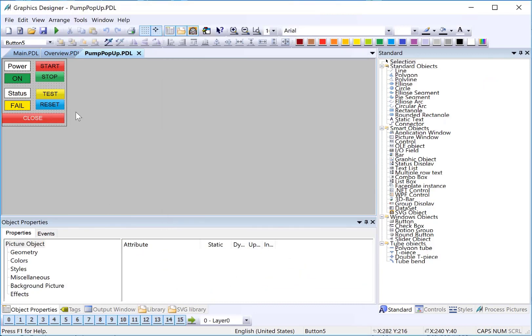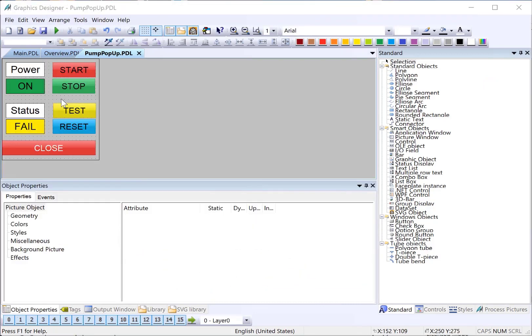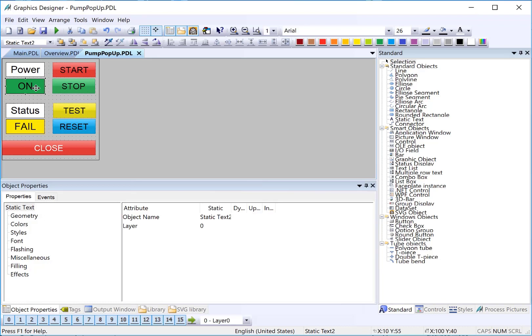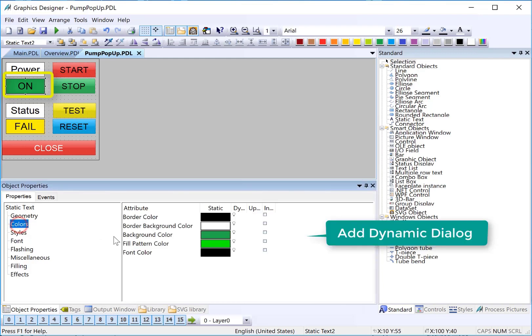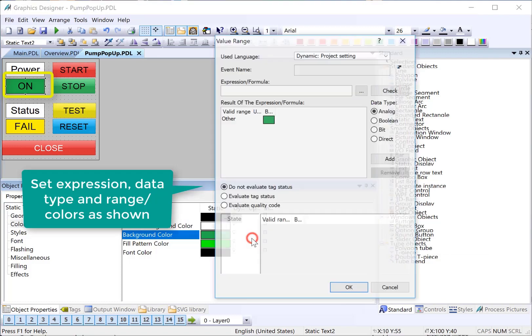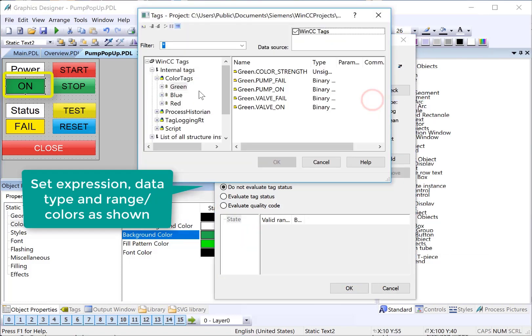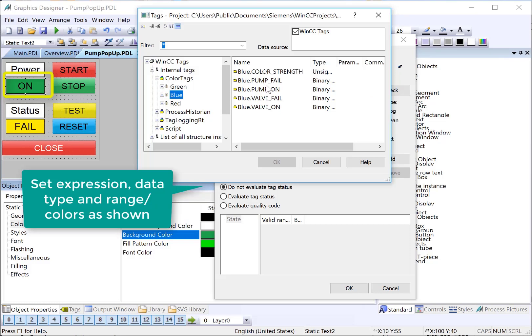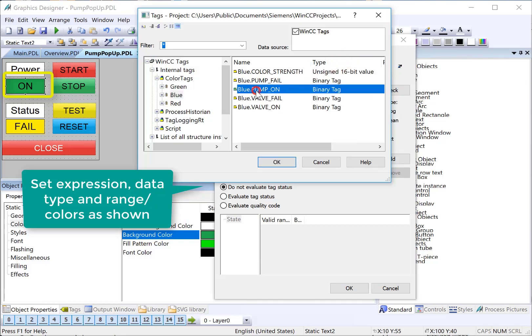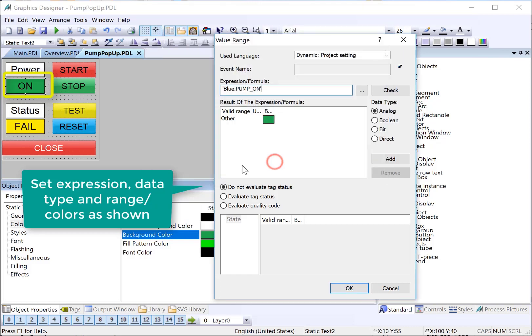And there's our pop-up screen. This pop-up screen is going to map to our color structure, so we need to add dynamics. We'll start with our on-off indicator. We're going to change both the text and color like we did on the face plates. So, we'll start with color. Choose dynamic dialog. We're just going to pick any one of these. It doesn't really matter. You'll see why in a moment. But this is going to be our pump on.